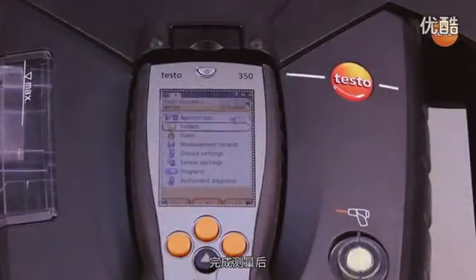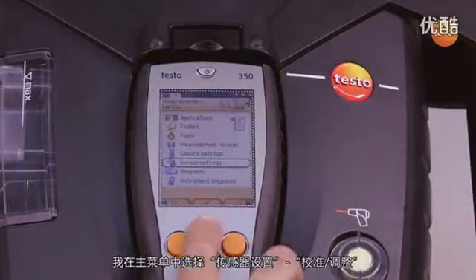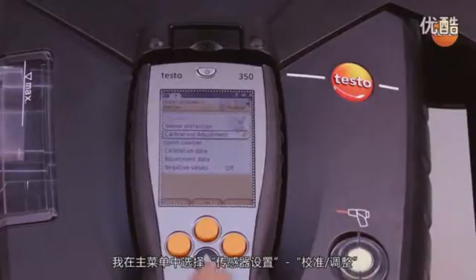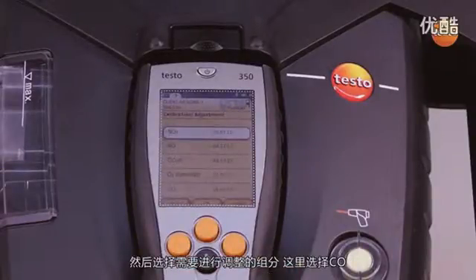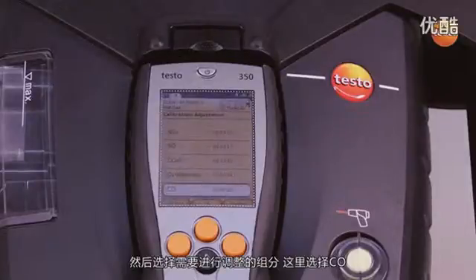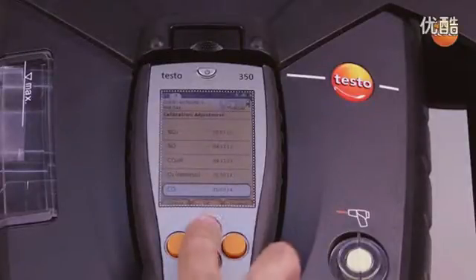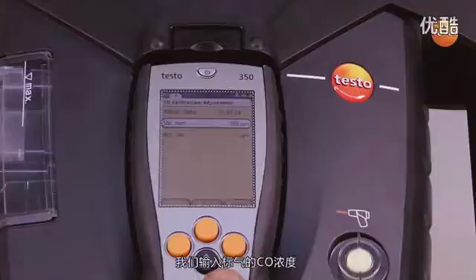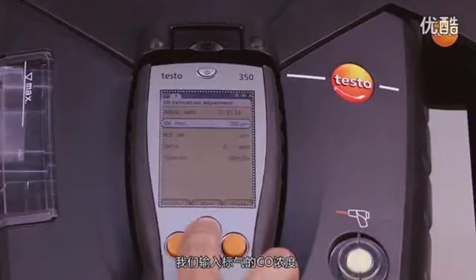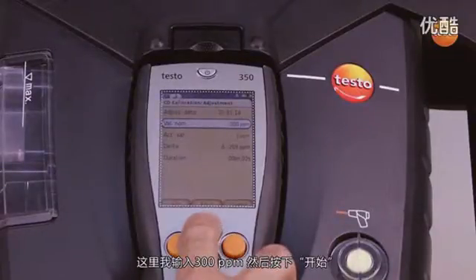After I finish the measurement, I select Sensor Settings and Calibration Adjustment in the main menu and select the components we want to adjust, in this case CO. Under Nominal Value, we enter the CO concentration in the test gas, in this case 300 parts per million, and press Start.